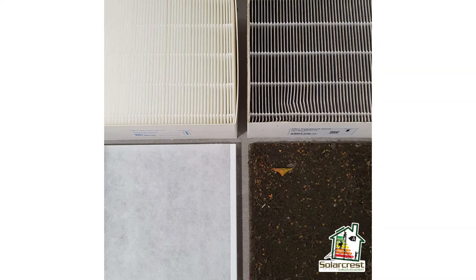I've got to quickly mention filtration because this is the reason you should be putting MVHR in your home more so than heat recovery. It's the only system that will filter the air that you breathe. Here's a standard G4 debris filter. All machines have one or two of these. One of them stops muck from outside coming inside the other one stops muck from inside clogging up your machine. This is what it looks like after three or four months. You've got leaf debris on there you've got insects and all of this black stuff is soot from the road and this filter is a lot away from a road. This is an F7 fine particle filter that stops pollen and other miniature particles from vehicle emissions like rubber dust. You can have one of these instead of one of these but bear in mind it's quickly going to look like that and you'd be constantly changing expensive F7 filters. The better machines have one of these to protect one of these so you've got both in there. This is what the filter looks like after three or four months and bear in mind all of this soot and these particles have come through this filter first so it's important to have both.